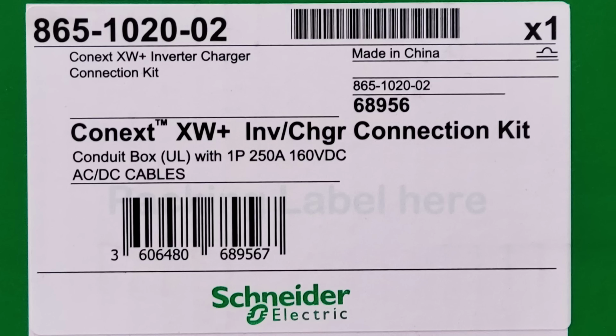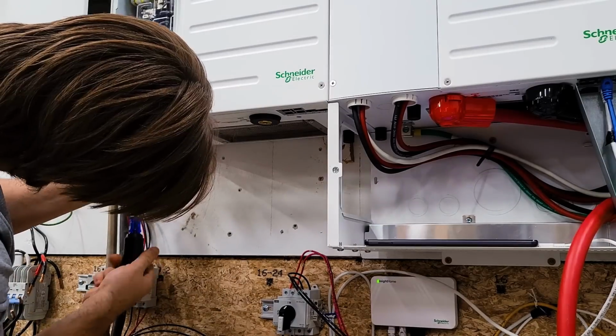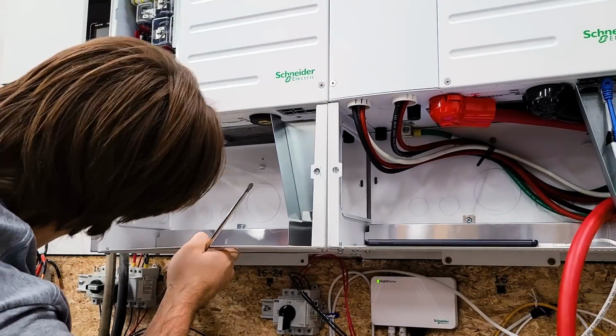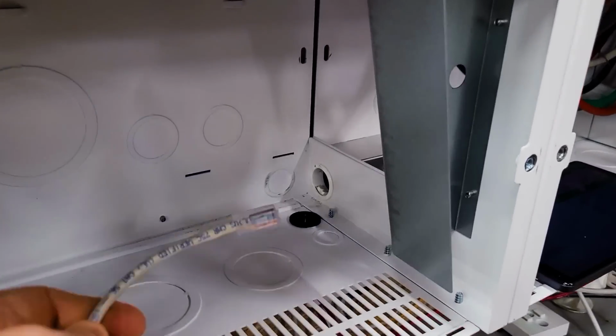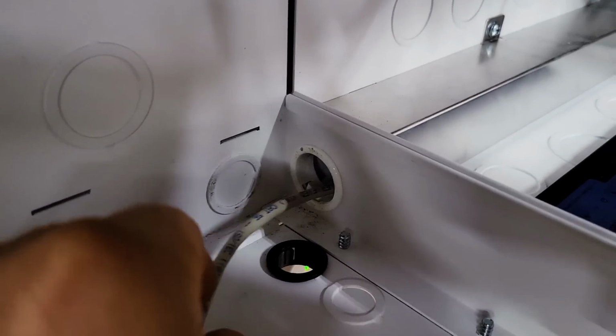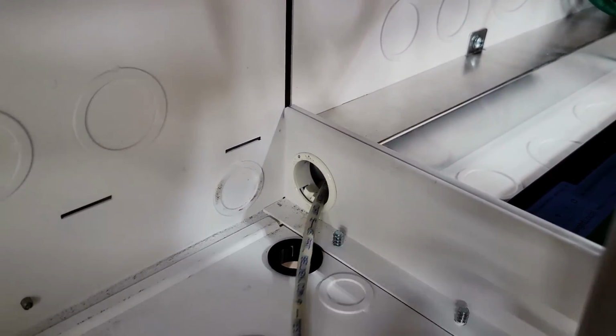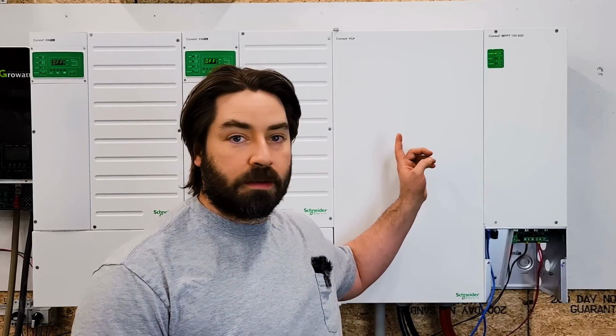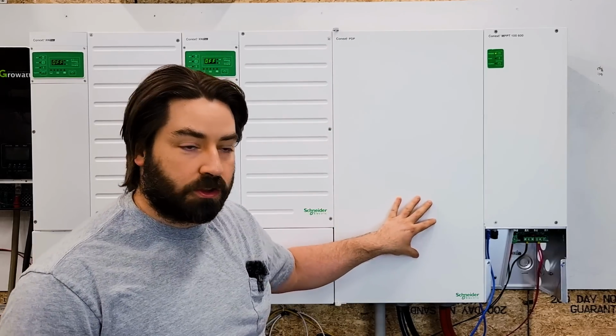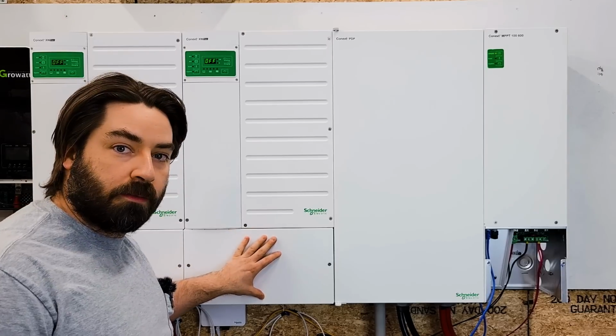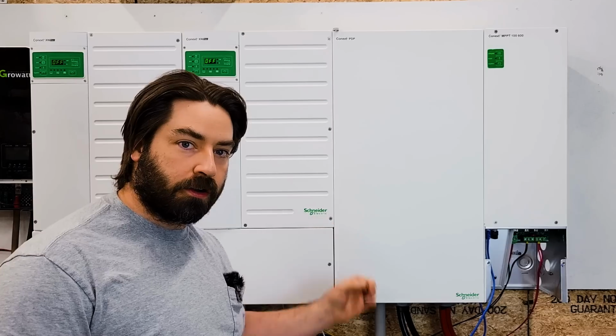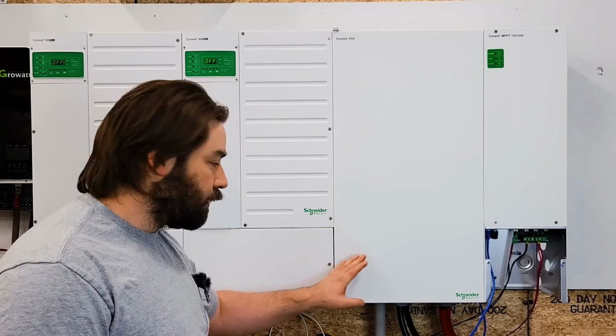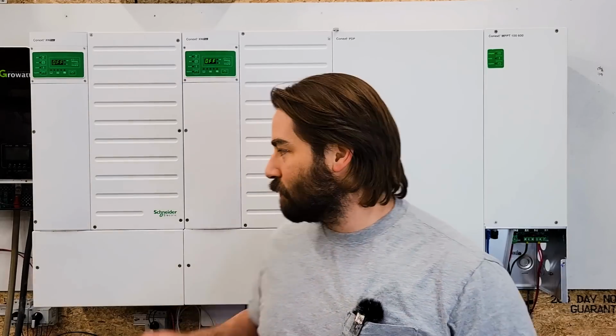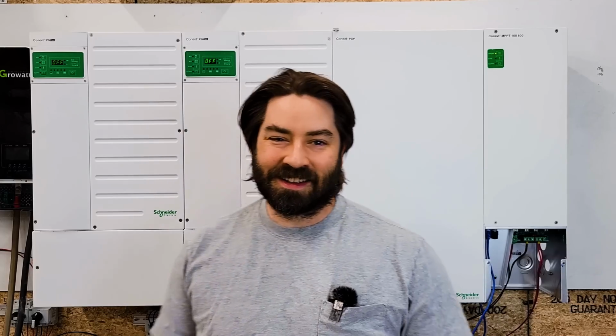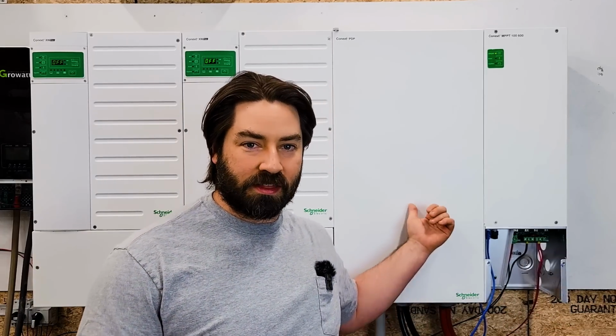And it comes with the wires, it comes with the wireway, it comes with the plastic bushings, not only for going from the inverter to the wireway, but also a smaller plastic bushing for the Cat5 communication wireway, which is a separate connection in the back so that the inverters can all talk to each other. That was nice that they included that, because the PDP is a large unit and it comes with one wireway. But Schneider does not include that smaller, I think it's a 3/4 inch plastic bushing, in this kit. But they do include the plastic bushing when you buy the inverter connection kit. I actually wish that Schneider would include that extra bushing on the PDP as well.